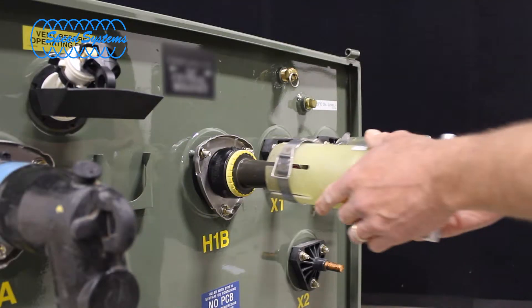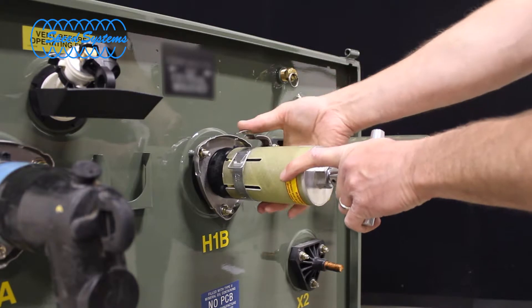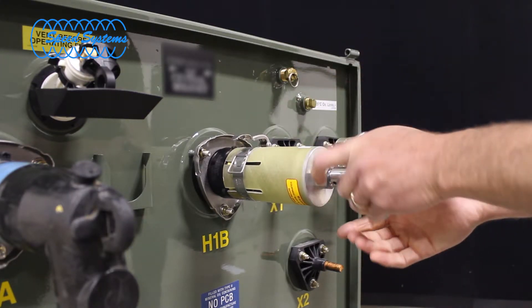Open the quick clamp lever to allow the insert to slide into the tool. Center the probe on the insert until the shoulder contacts the bottom of the tool's tube and close the quick clamp lever to securely clamp the insert in the tool.